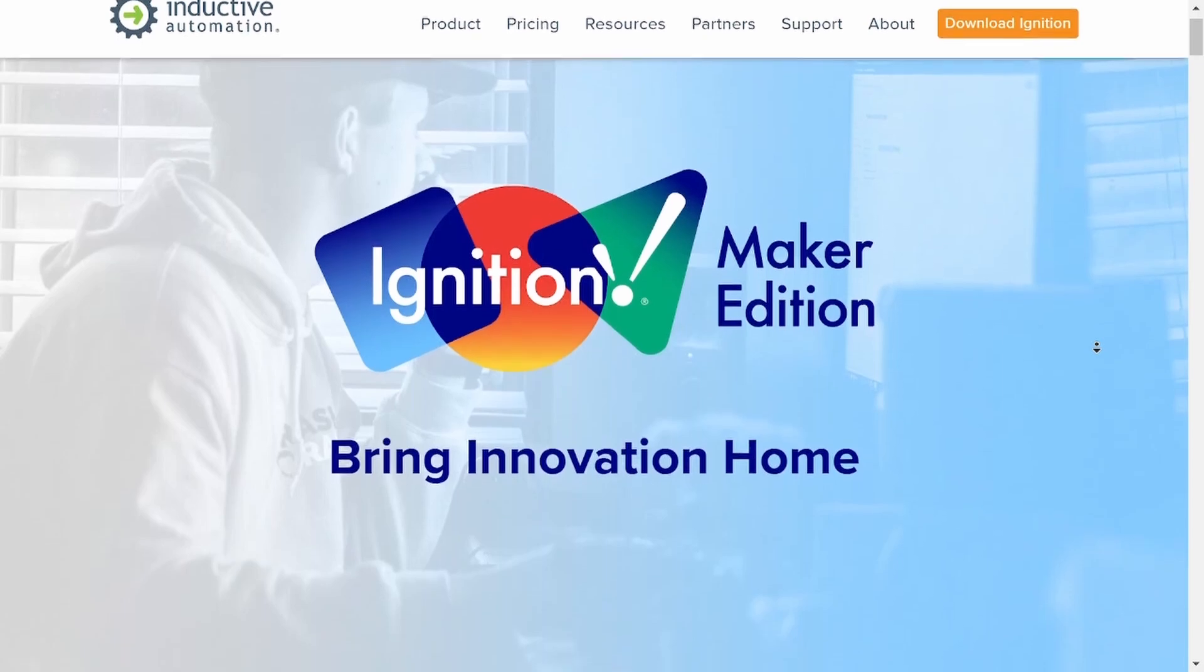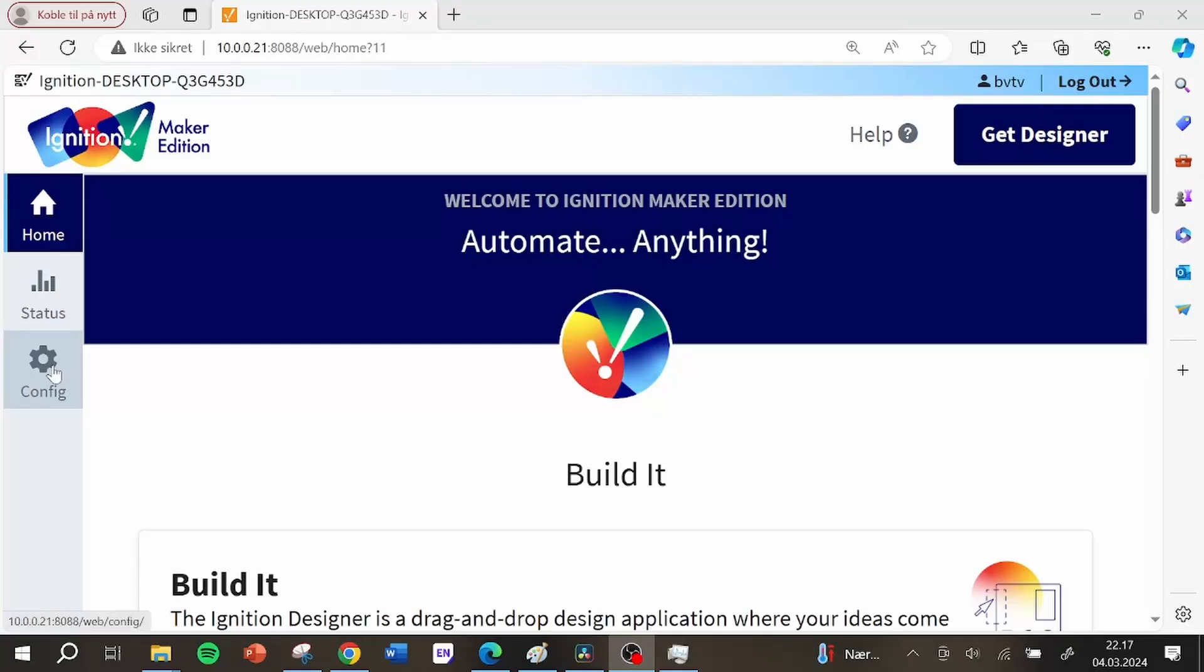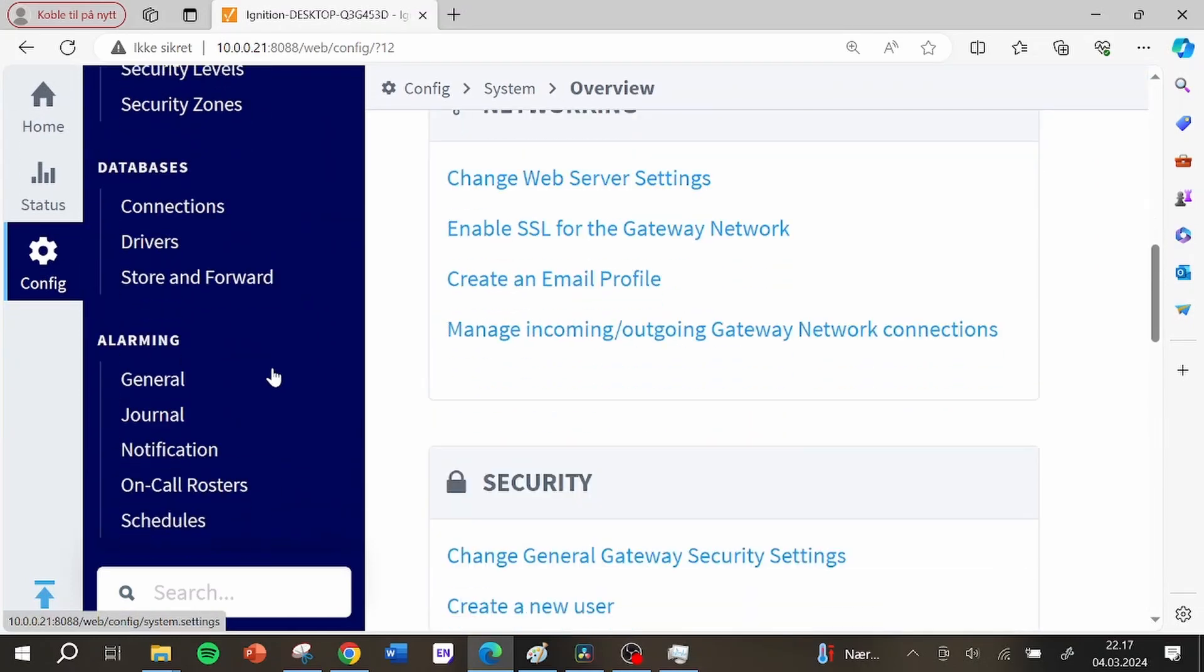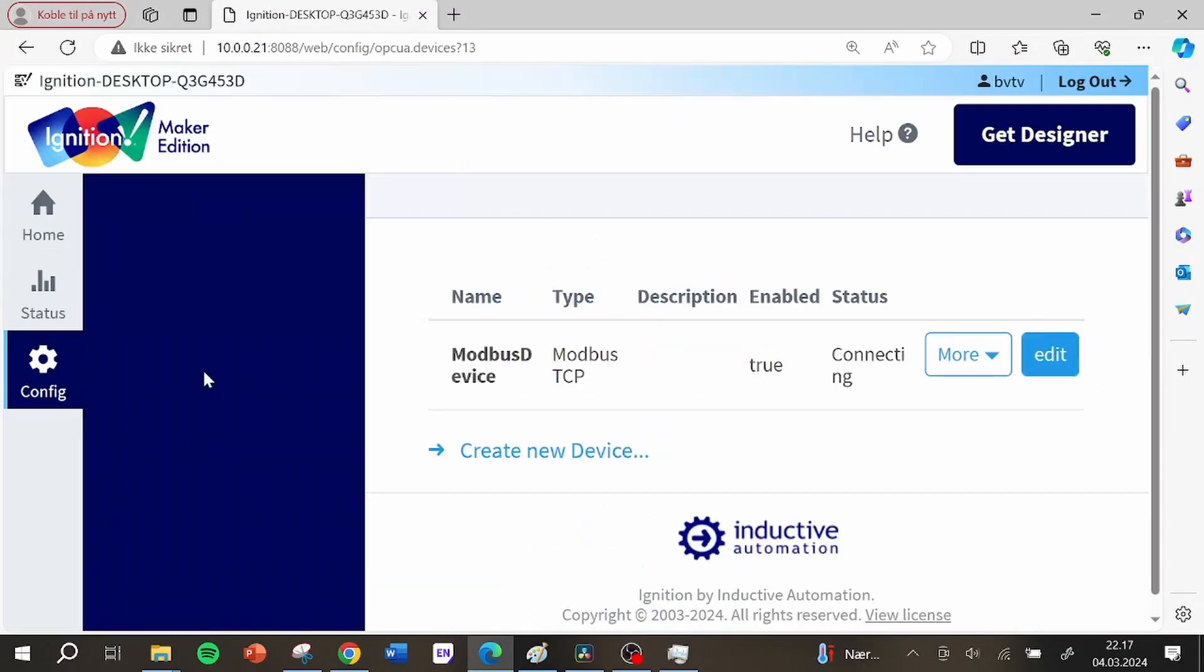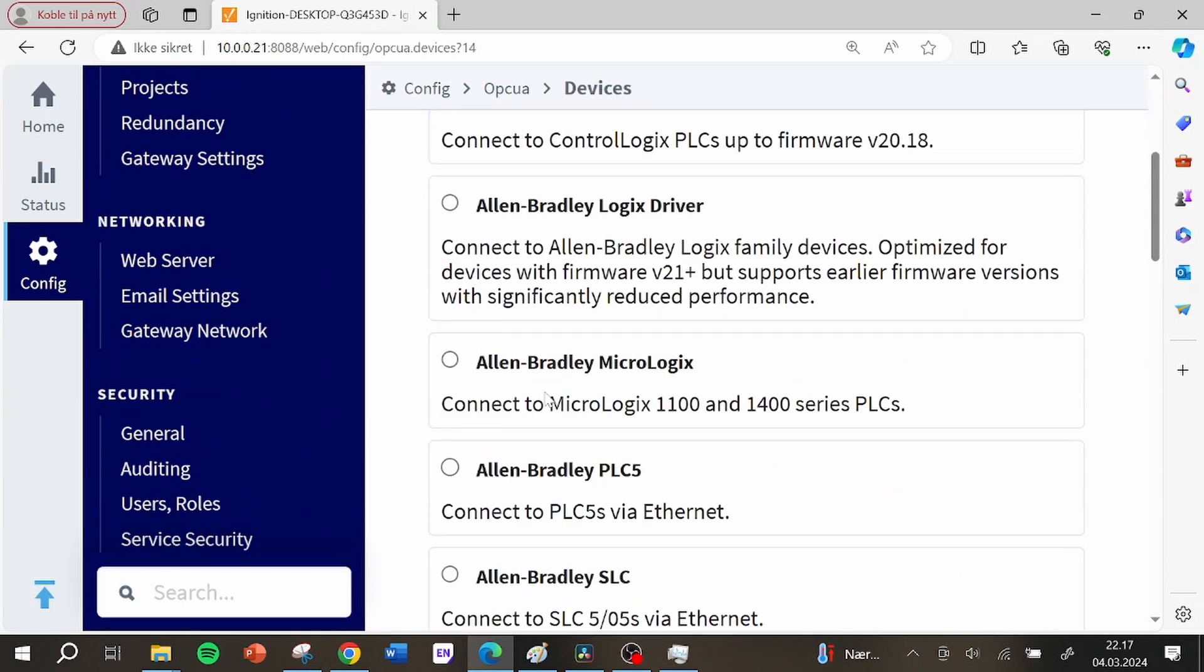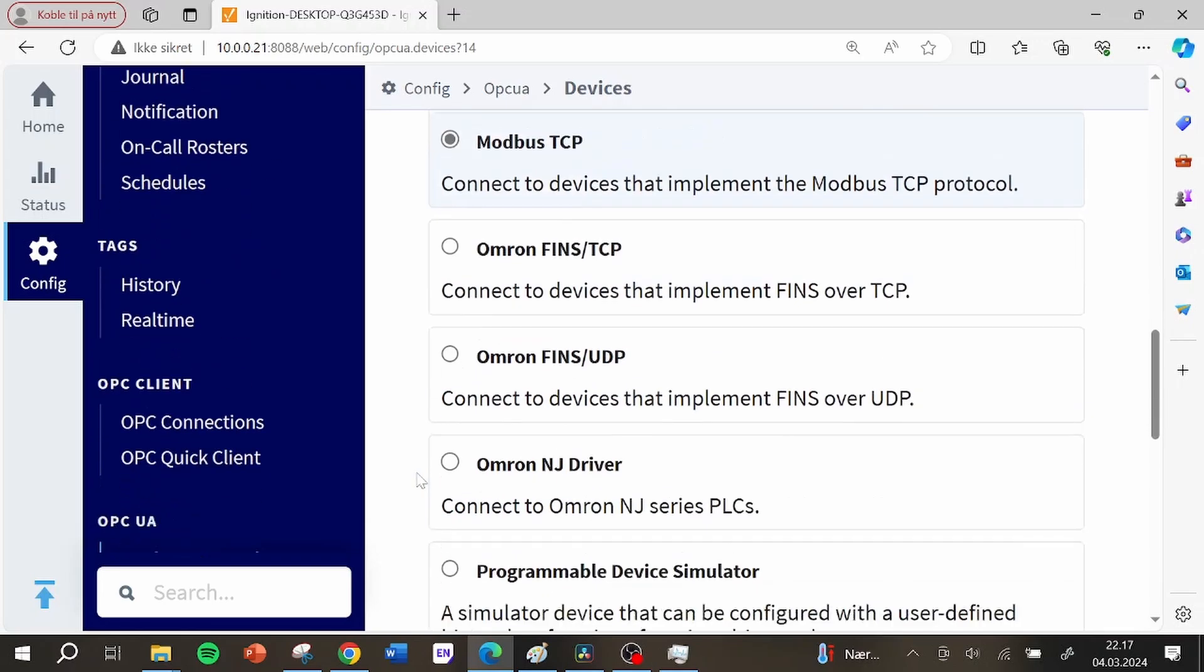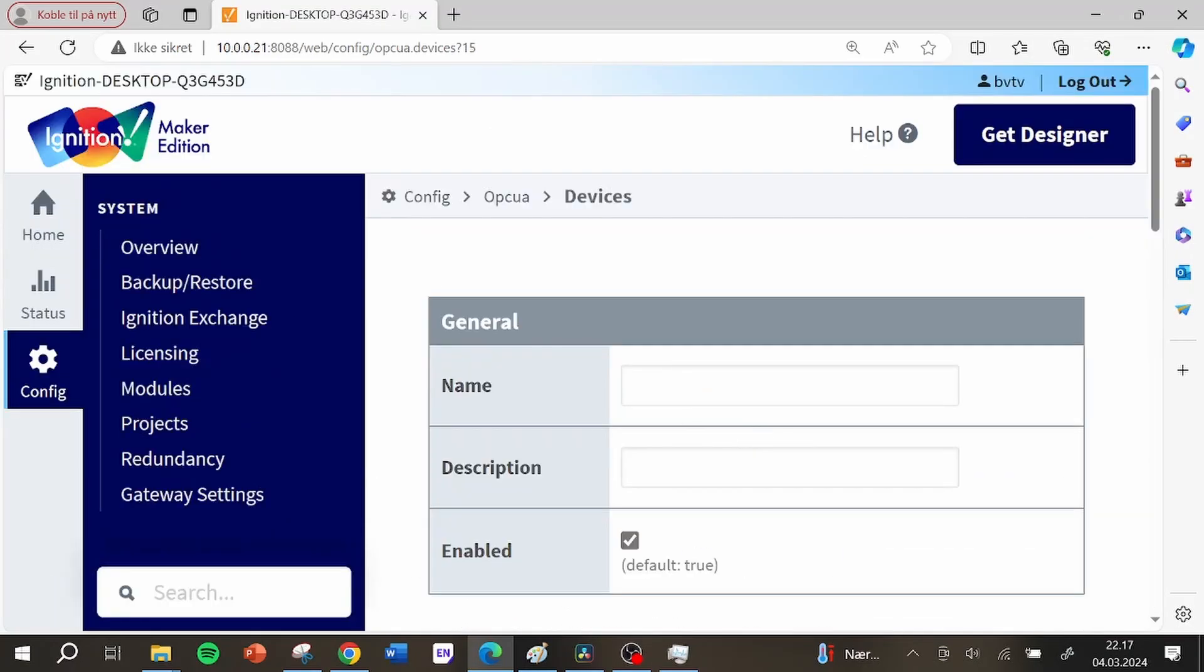After downloading and installing ignition maker edition on my computer I got access to the ignition settings in the web interface. On this page you can configure almost any aspect of ignition but what I did was to add a connection to my Modbus device. To do this I navigated to config, OPC UA and device connections. On this page I added a new device and found the type Modbus TCP.